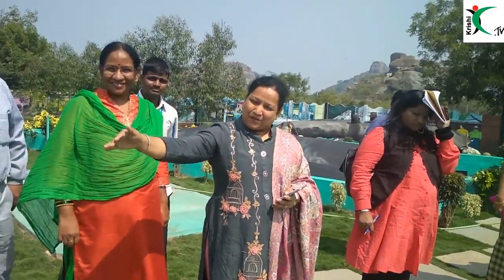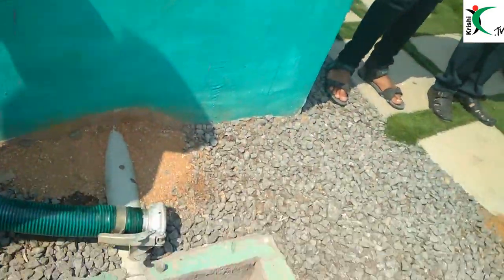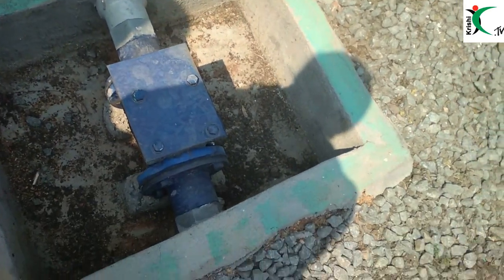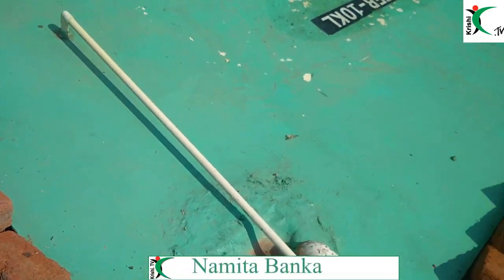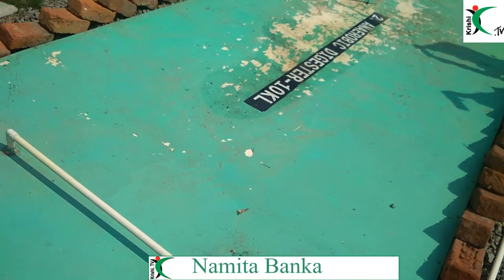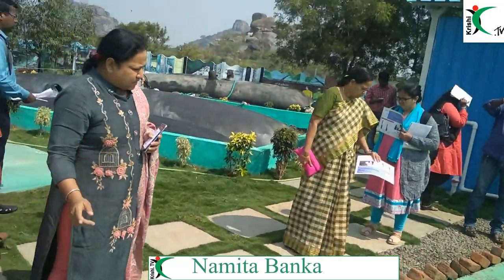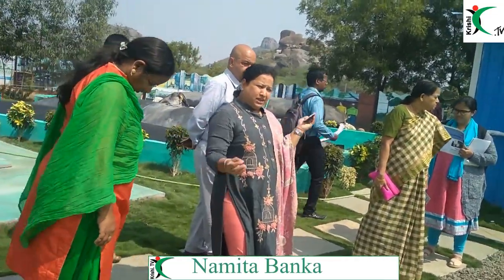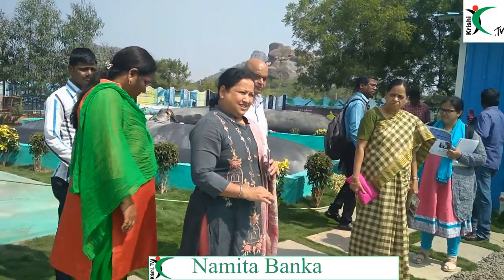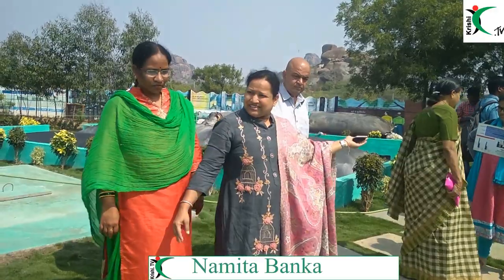Sludge is coming there. From there, it gets screened. Then from here, it comes to this tank where we are doing two processes. One is homogenization of the mixture, and second, we are doing the recirculation. This process takes about half an hour to 40 minutes. And from here, it goes to our static mixer where we do the flocculation inline. We're doing an inline flocculation. There's no tank for flocculation. That we can go and see.